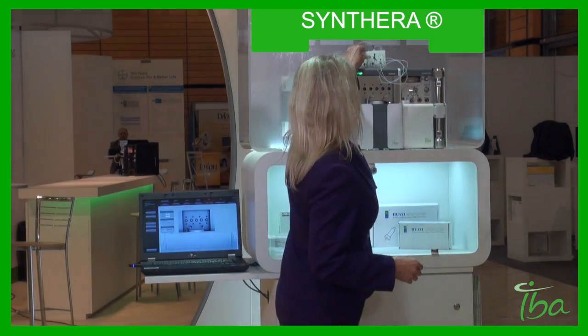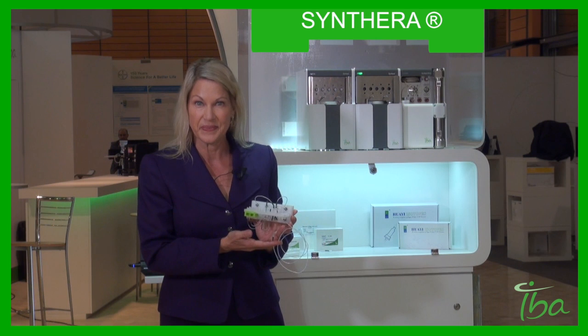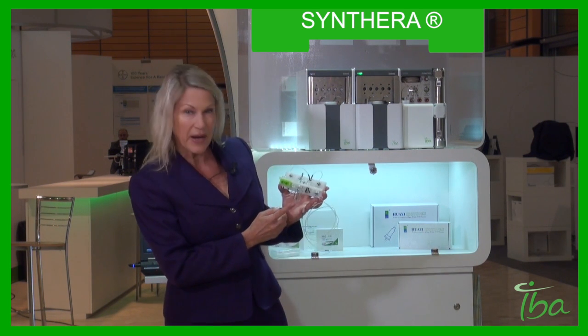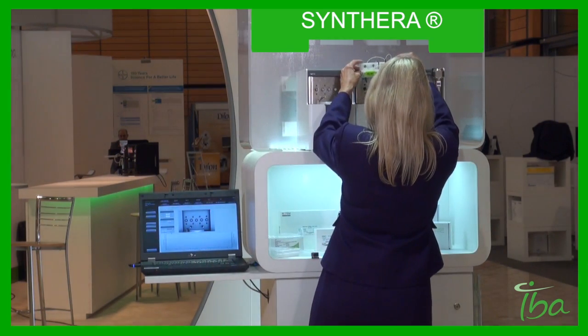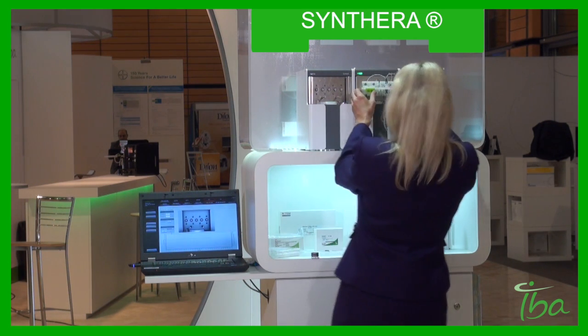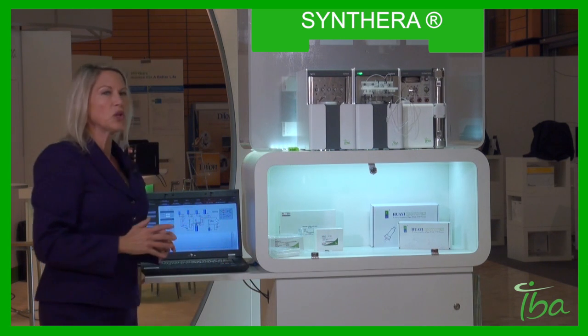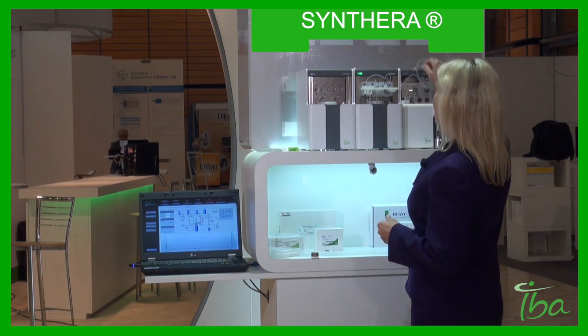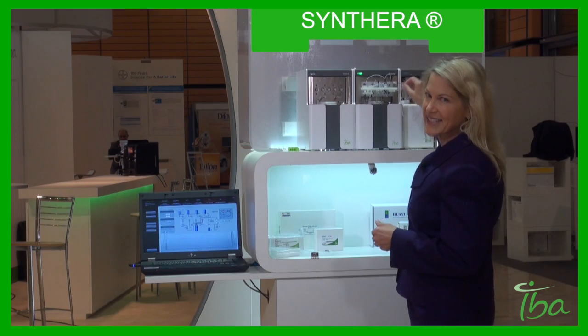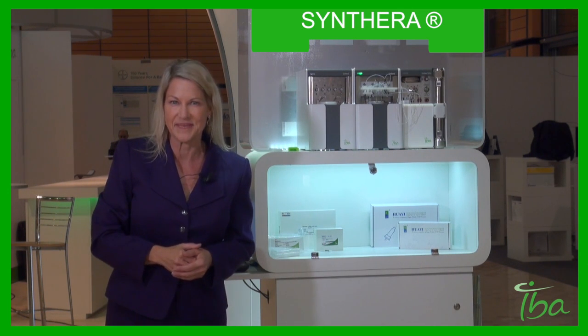This unique feature stands in the disposable integrated fluidic processor system — in short, IFP. Really easy to use: first prepare the IFP with the reagents and Sep-Pak cartridges and slide it onto the IFP holder. I'll remove the needle support tab. On the user interface, I click the load button. The system will go through an automatic check. I connect the IFP to the product line, and my system is now ready for the automated synthesis process. When I click resume, the synthesis will start immediately. Your FDG dose will be ready after a run time of less than 30 minutes.